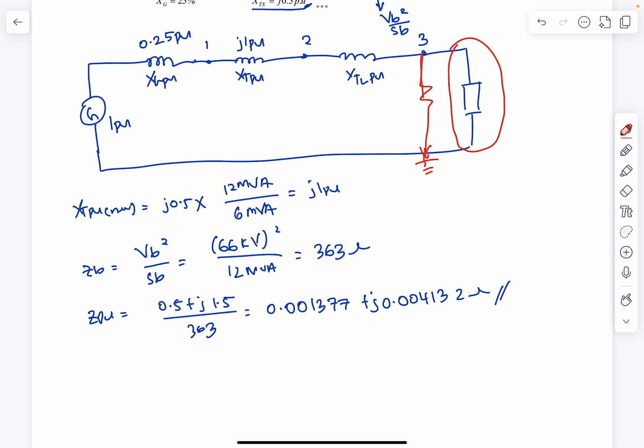If you look at this diagram, it's a series single-phase equivalent diagram. So how do you calculate ISC? ISC per unit equals V divided by Z total, by Ohm's law, since the load is ignored due to the short circuit current. So ISC per unit equals VS divided by Z total, where VS equals 1, and Z total is XG per unit plus XT per unit plus XTL per unit.